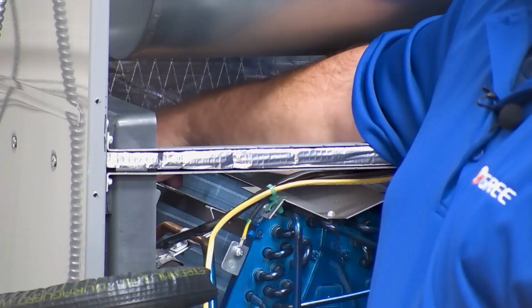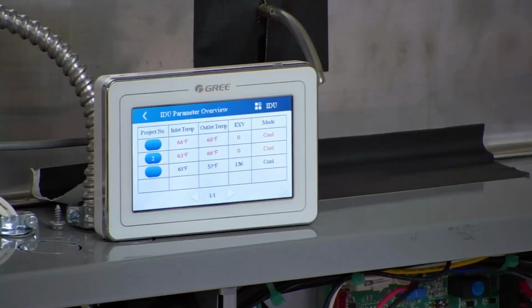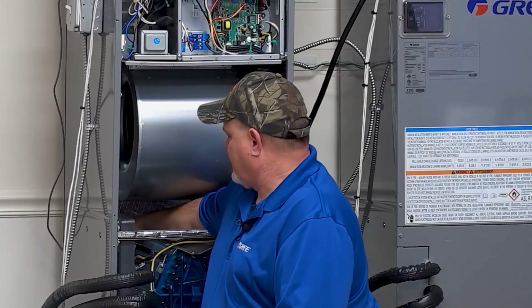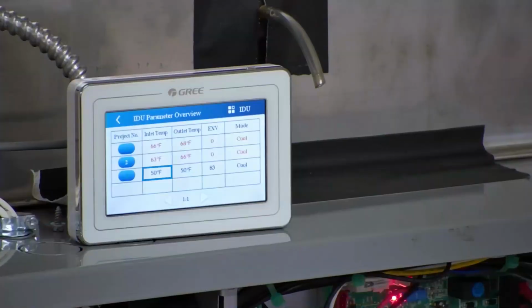Now let's manually open it and see if we can get that temperature to drop. There we go. Oh, look at that, 59 degrees. We definitely got refrigerant starting to flow in there because the line's starting to frost. There we go, now we're starting to get some temperature drop.